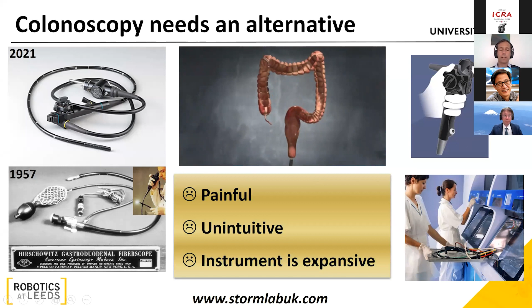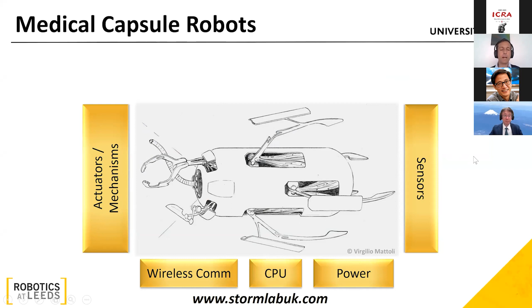They must possess proper actuators and mechanisms to interact with the surrounding anatomy and move around in a controllable fashion. They need sensors, including vision, to enable clinical diagnosis and other functionalities. They need a brain or a CPU, communication with the outside world and the operator, and finally, they need power. All of this needs to be integrated in a limited volume, so size becomes the most important cross-cutting constraint. Typical target values for a capsule robot are a diameter of 11 millimeters and a length of 26 millimeters to allow for oral intake, or a little larger volume, typically 3 by 3 by 3 cubic centimeters, for application in the colon via retrograde access.